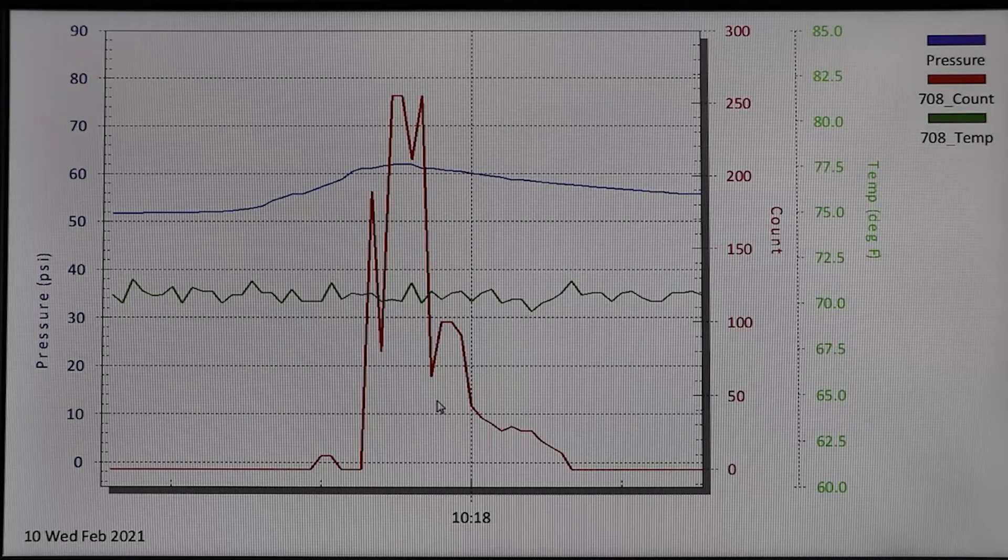Reviewing the acoustic signal in red we can see the rapid increase and decrease in acoustic counts during the event. This rapid change in acoustic signal indicates the valve is chattering as it opened and closed rapidly. Chattering of a relief valve can be damaging to seating surfaces and can be due to excessive inlet line losses or a valve with incorrectly adjusted blowdown.